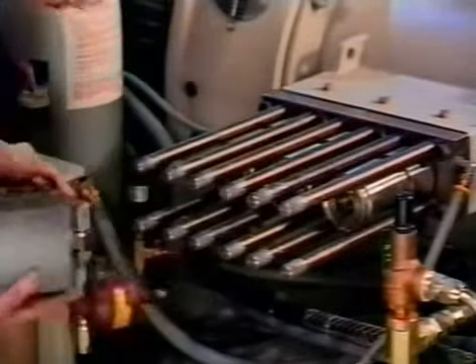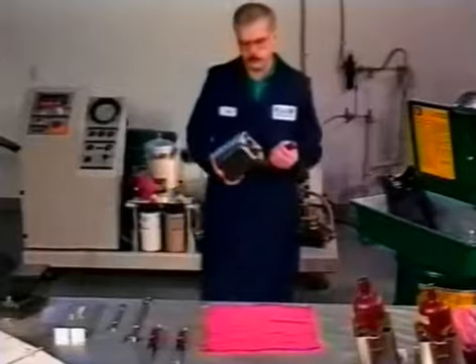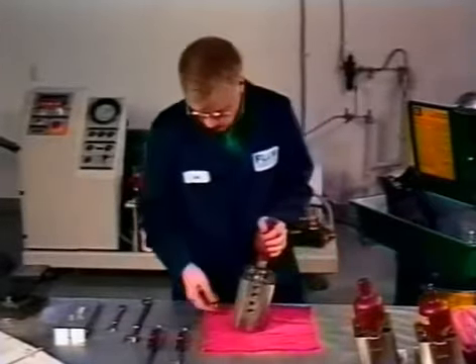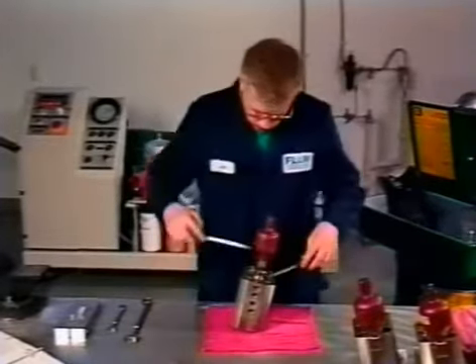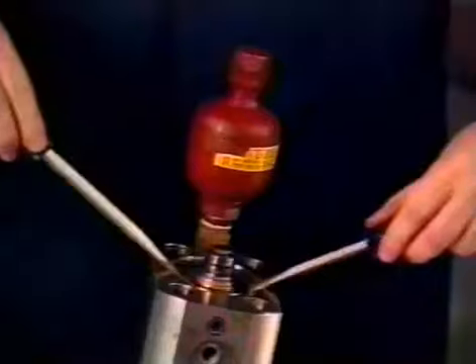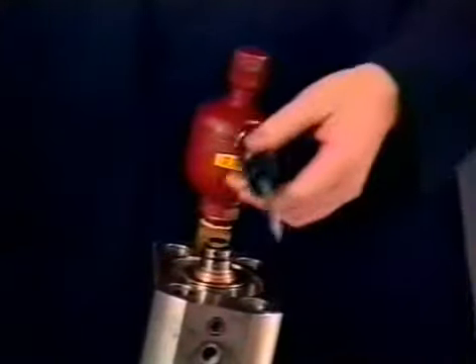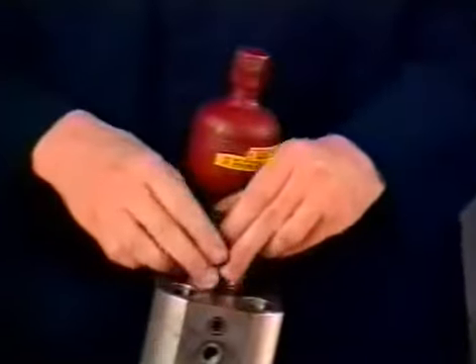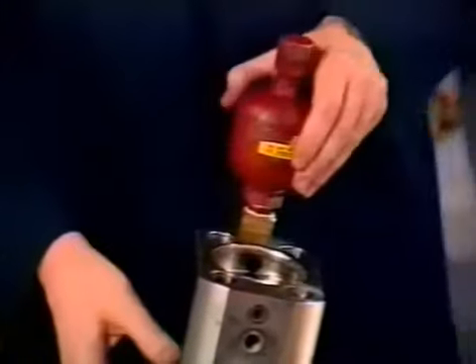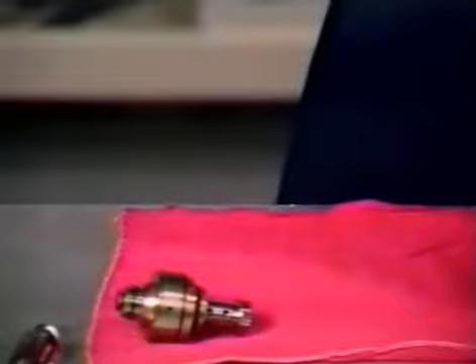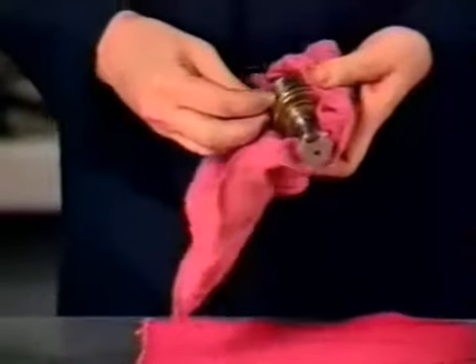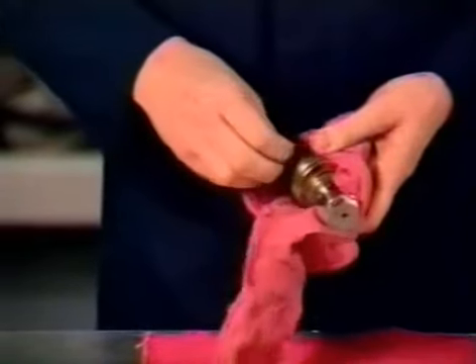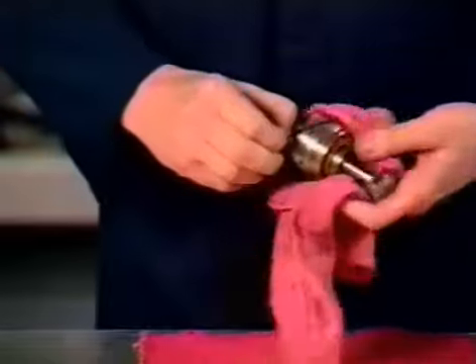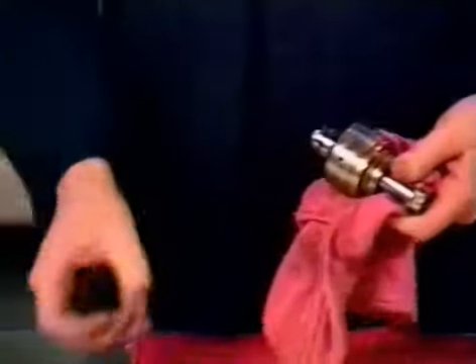Place the end cap on a workbench. Then, place 2 small screwdrivers in the groove on the check valve body and pry the check valves from the end caps. Remove the O-ring from the outside of the check valve body and secure the check valve in the special check valve clamp.